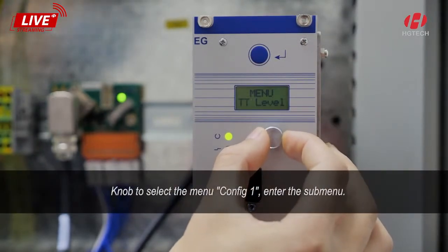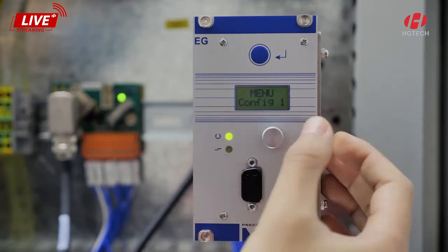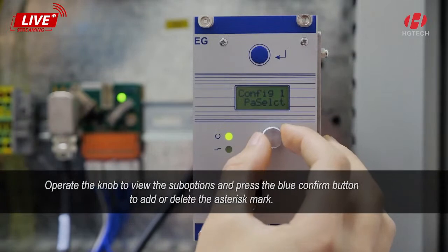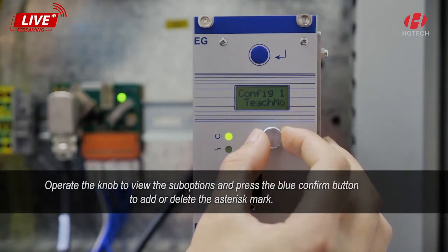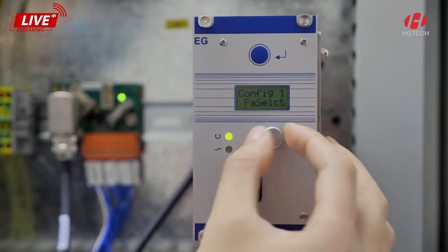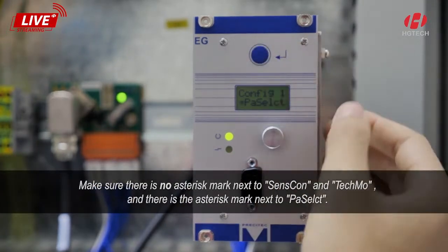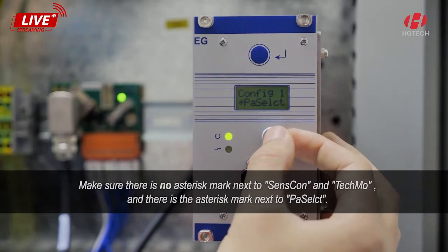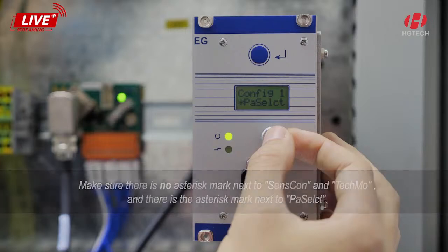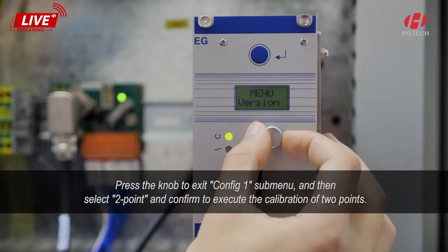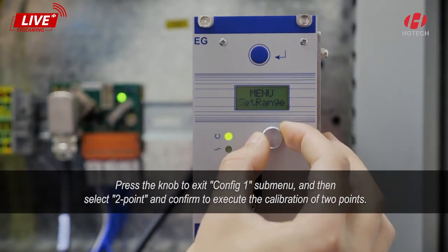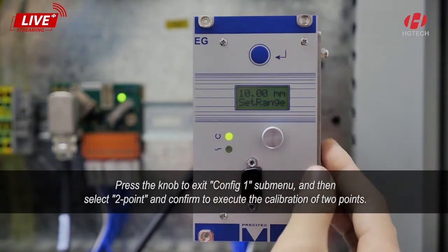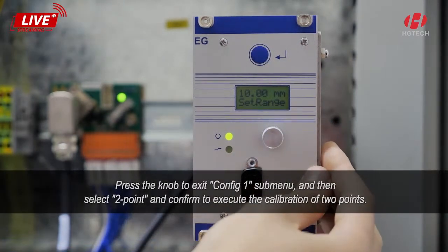Use the knob to select the menu config 1 and enter the sub-menu. Operate the knob to view the sub-options and press the blue confirm button to add or delete the asterisk mark. Make sure there is no asterisk mark next to SensCon and TechMo, and there is an asterisk mark next to PaSelct. Press the knob to exit the config 1 sub-menu, then select the 2 points and confirm to execute the calibration of 2 points.